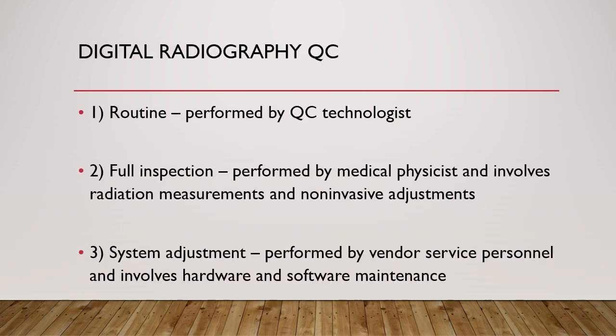The digital QC program is performed routinely by the QC technologist, and the routine procedures would be on the protective apparel and also on the repeat analysis. Full inspection is performed by the medical physicist and involves radiation measurements and non-invasive adjustments. System adjustment is performed by the vendor service personnel and involves hardware and software maintenance.